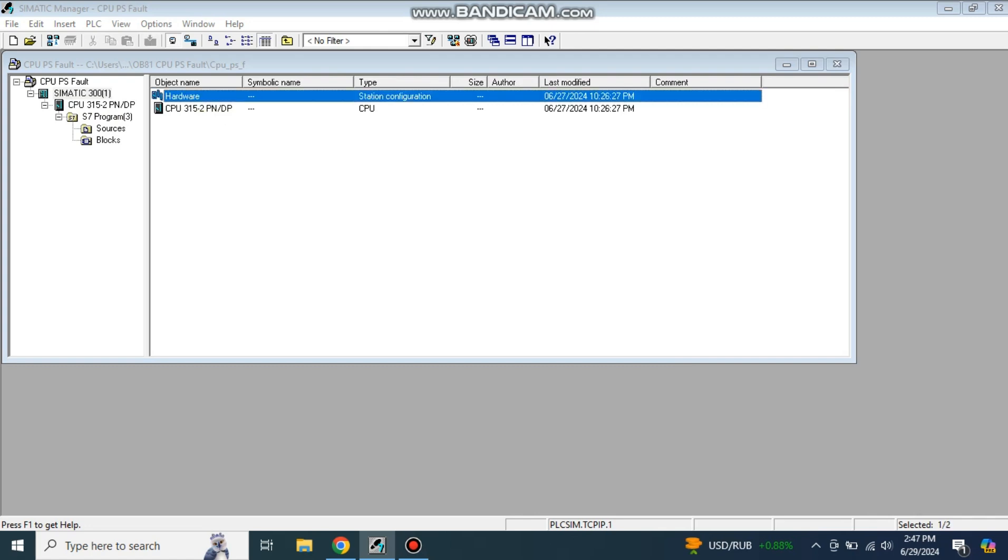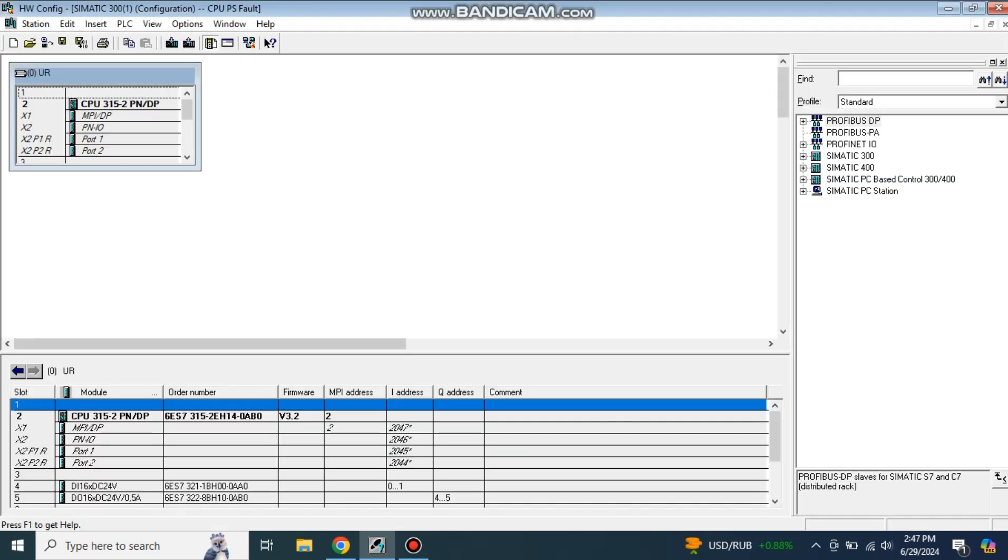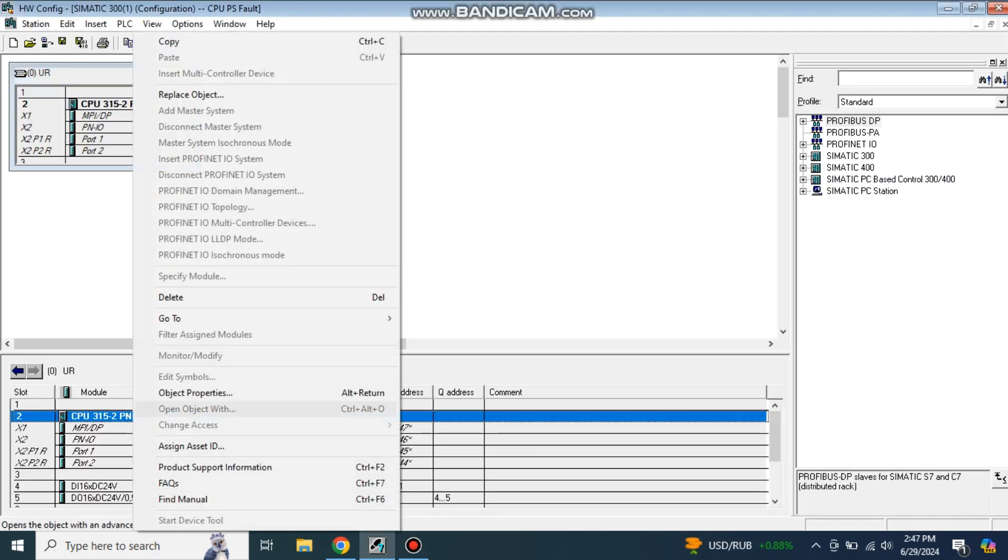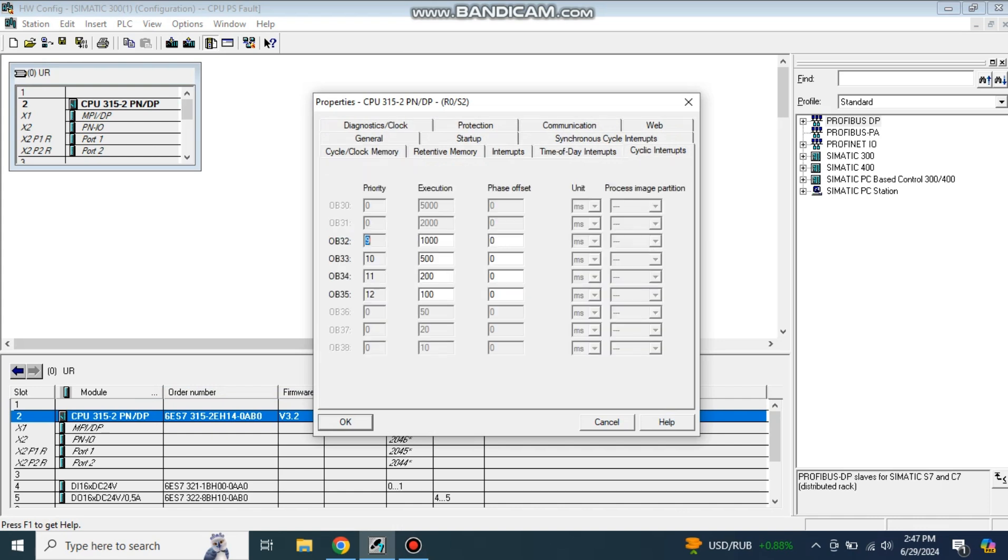Go to hardware and take the properties of this CPU, object properties, and go to cyclic interrupts. My CPU which I have selected, 315-2 PN-DP, actually supports four cyclic interrupts from OB32 to OB35.